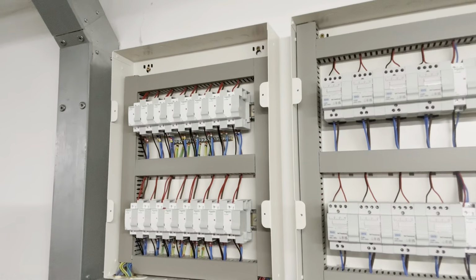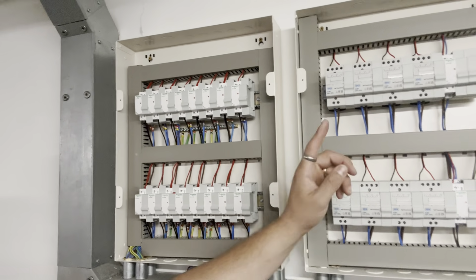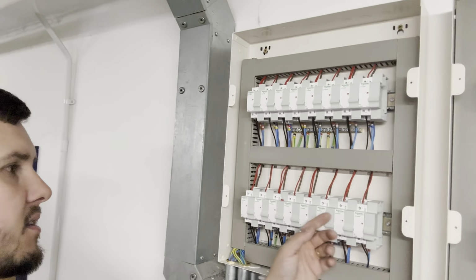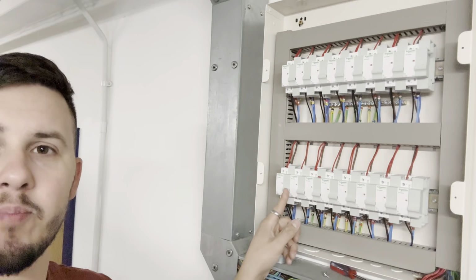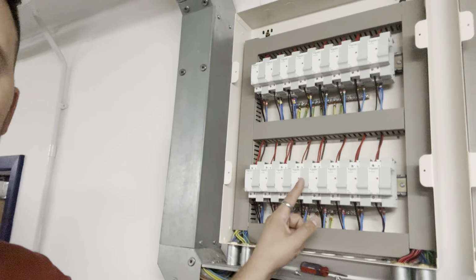2 panels are up now, so you can see all the transformers here and things, looking really smart, humming away. We've put a blank in between every single contactor and transformer for heat dissipation, because even though a contactor is effectively just a switch, the coil does generate quite a bit of heat. If you had them all bunched up, you want to make sure they've got space so they don't get affected too much by thermal effects, otherwise they'll have problems down the line.